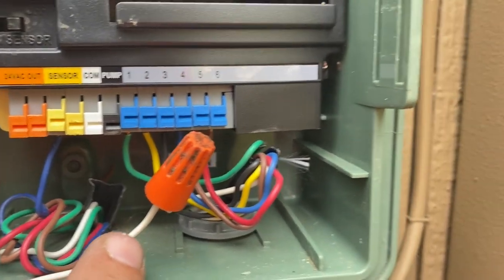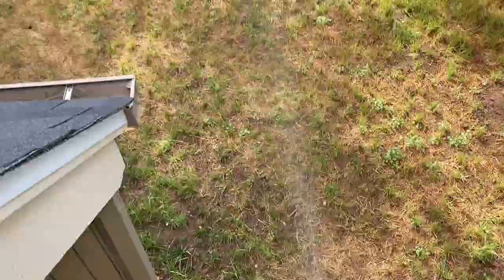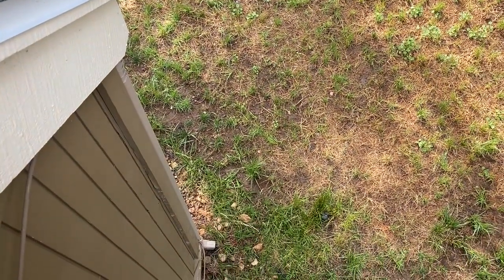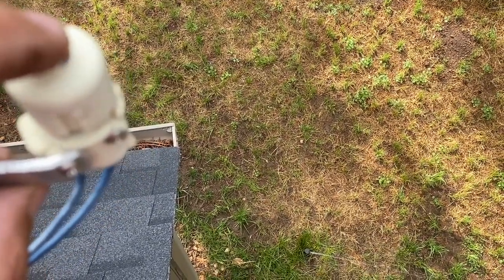To test it, all you do is hold this little button down — it turns off. You can hear it click off. Different angle: I push it down and it goes off, let go and it comes back on. So this one's working. You can see that sprinkler head over there — boom, job done.